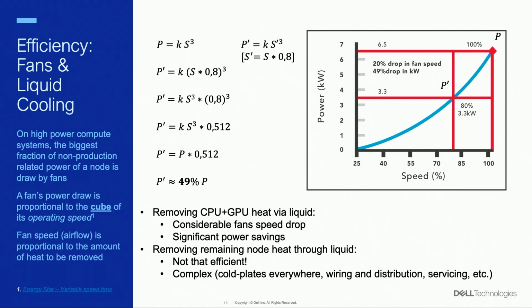So we are able to reduce the rotational speed of the fans much more significantly. There is no need to try to cool everything with liquid, because it wouldn't be that efficient in any case. Also, liquid cooling would have overhead and would add additional cold plates that would need to be deployed on every DIMM, disk, NIC, and so on. That would become a real nightmare for servicing those devices. So we still have a relatively simple server design, but with this hybrid cooling solution. This is very important.